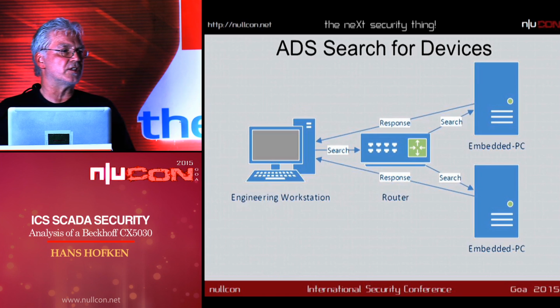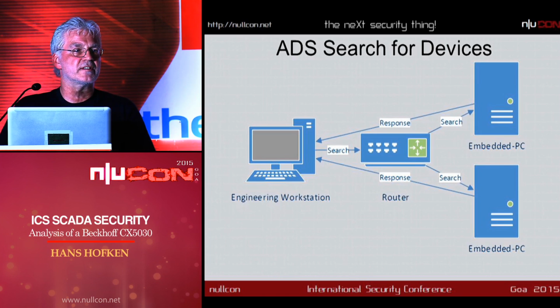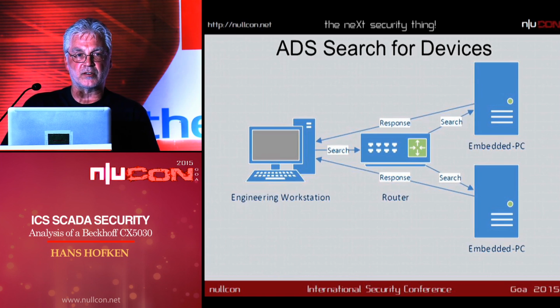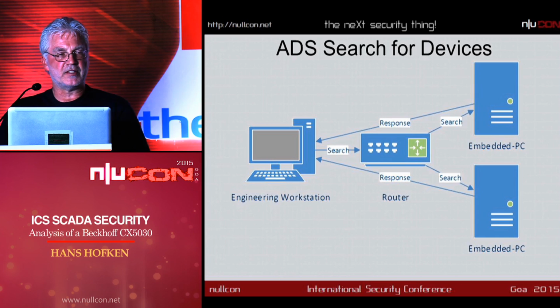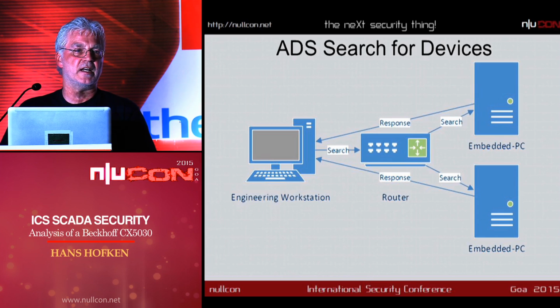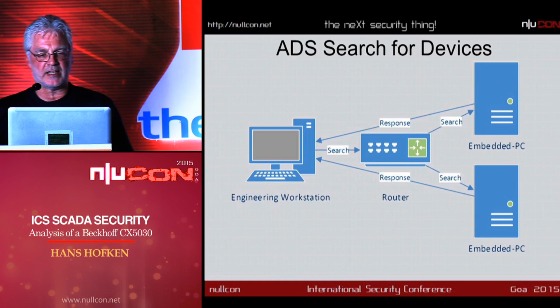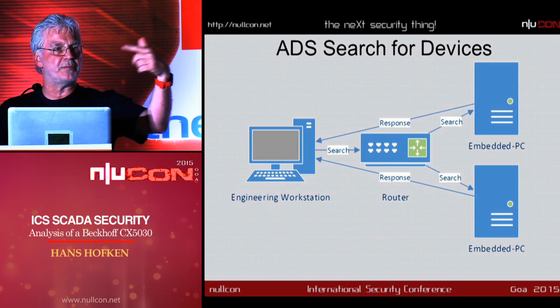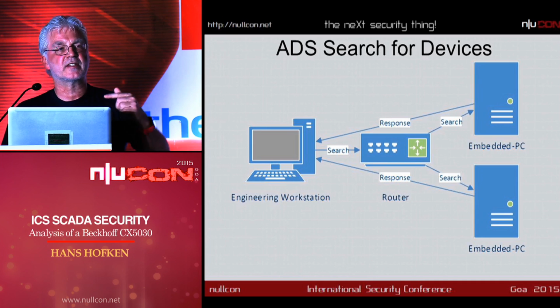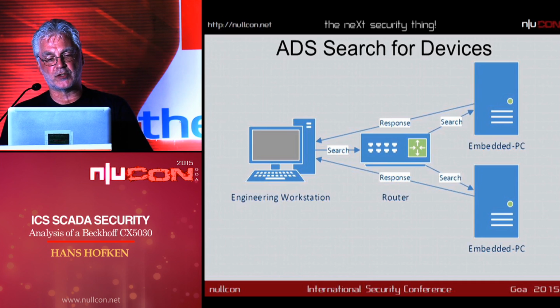First of all, the TwinCAT System Manager is able to search for PLCs. It works like this: the engineering workstation sends a search. In this picture you see a router, though it could also be a switch. If it's a switch, you can send a UDP broadcast. If it's a router, you must know the IP address of the embedded PC, the PLC, and look for every IP address to search for PLCs. You have to scan the complete IP range for that subnet.